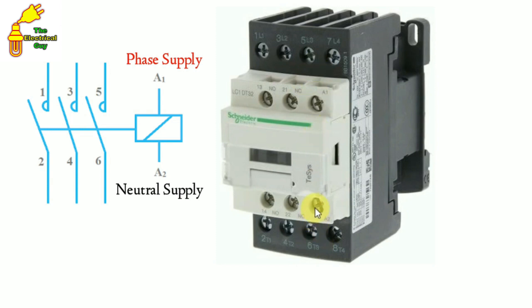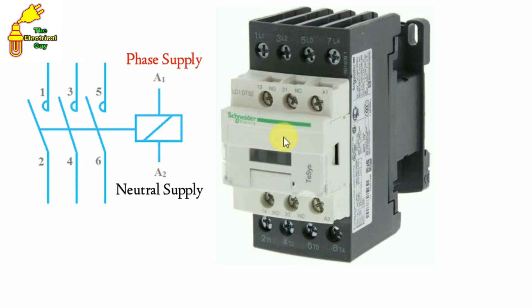When at A1 phase supply and at A2 neutral supply is provided, this contactor gets pickup. After pickup, the auxiliary contacts inside — NO and NC — get changed. It means the auxiliary NO contact will become NC after contactor pickup, and the NC contact becomes NO.